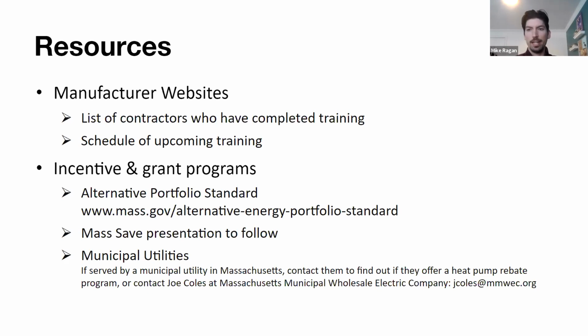And that loop is being served by water source heat pumps in individual spaces. It's not the most efficient way of delivering to the space, but it offers the ability for simultaneous heating and cooling for every individual unit by having that. And that would work by circulating the 90-degree water. If it's in heating, we add heat to it in order to get it up to that level, cooling, vice versa, et cetera, just like that. Anything hydronic related, I would certainly caution myself from just speaking in broad terms on, because they have very nuanced answers when it comes to the hydronic side.